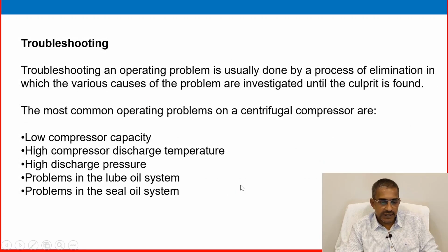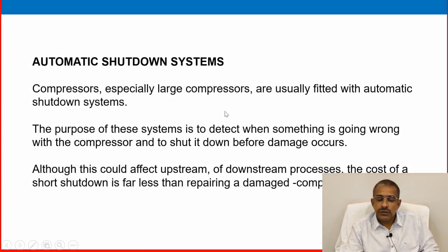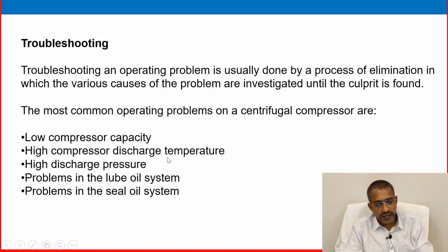So another step is troubleshooting. Troubleshooting an operating problem is usually done by a process of elimination, in which various causes of the problems are investigated until the culprit is found. The most common operating problems in a centrifugal compressor are low compressor capacity, high compressor discharge temperature, high discharge pressure, problems in lube oil system, problems in seal oil system. So these are the troubleshooting areas. You have to go with your operating manuals and standard operating procedures. So you will understand that and how we can troubleshoot these various situations that arise.